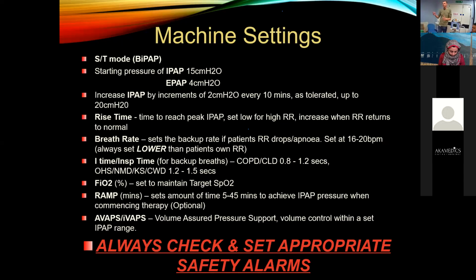It's important because if you've got patients that are very tachypnic and you have your rise time set long, the machine synchronizes with the patient. So when they start to expire, the machine will switch back to EPAP, even if it hasn't delivered the IPAP pressure that you've asked. So we recommend you have your rise time set low for patients with a high respiratory rate. So 25 plus, we would set our rise time low.